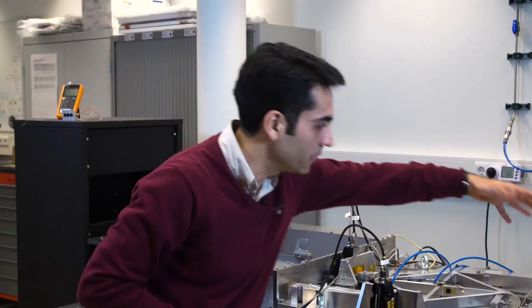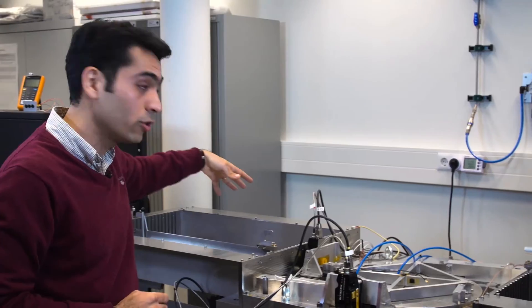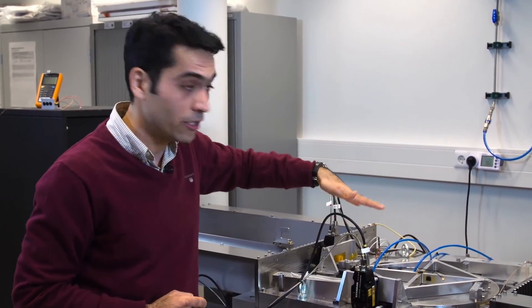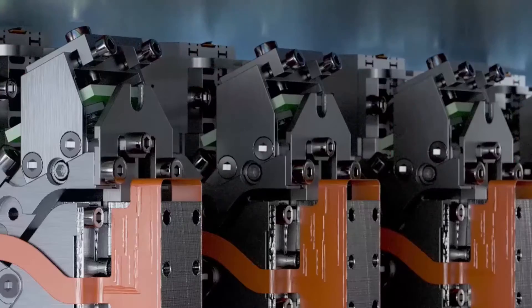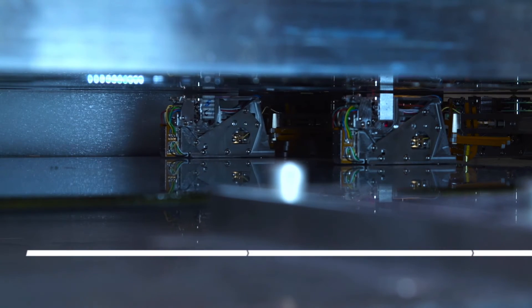From two sides you see these mini AFMs that are stacked, or so-called in parallel, from two sides. The wafer is positioned here. From two sides you position the mini AFMs and each of them measures a specific area on the wafer. Therefore, by finishing the measurement you get in parallel many site measurements on the wafer.